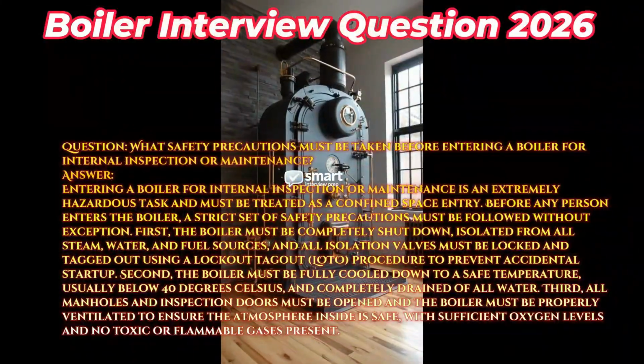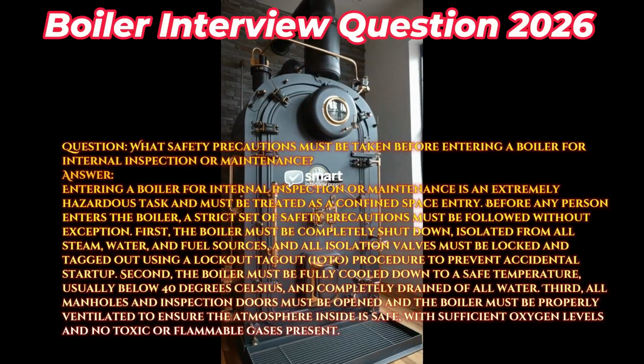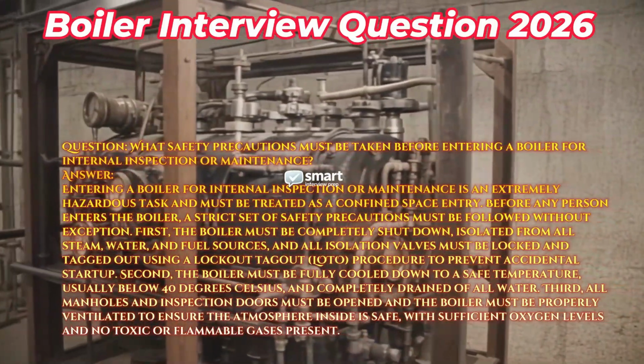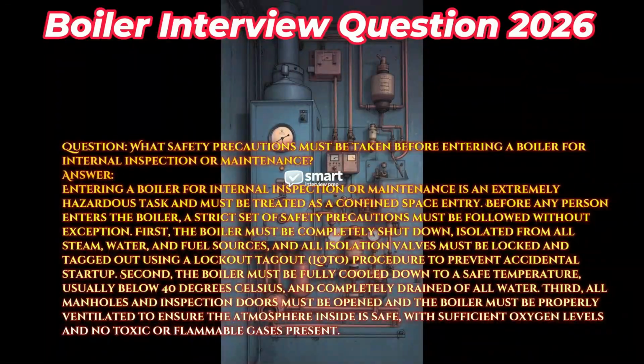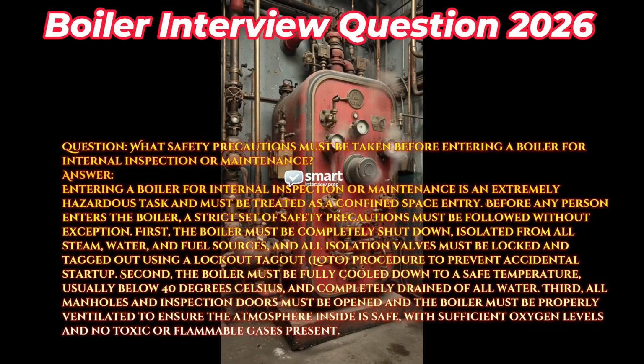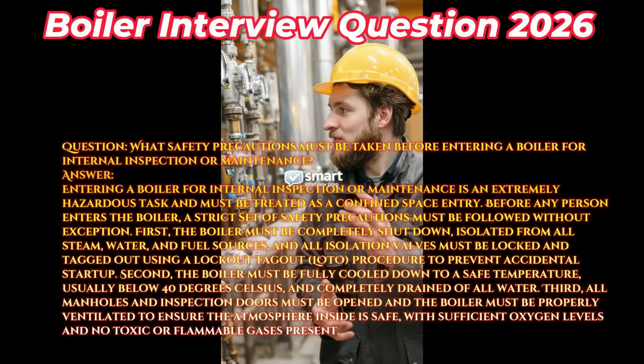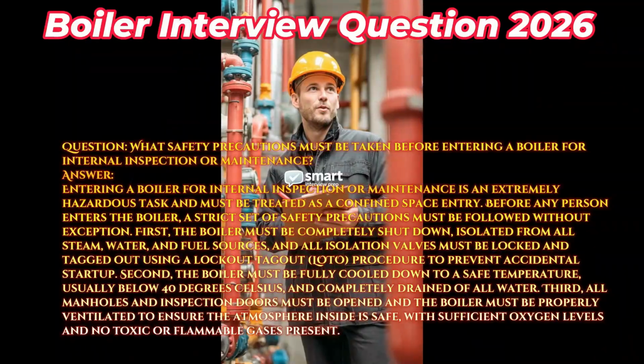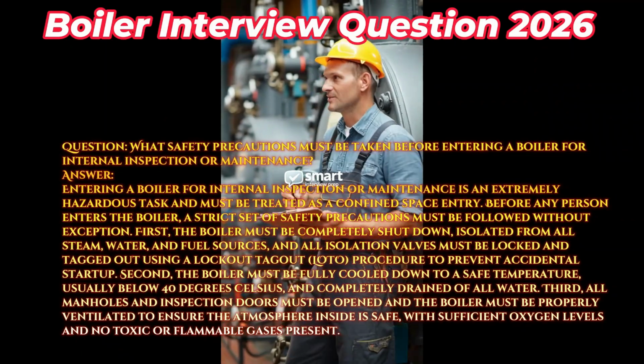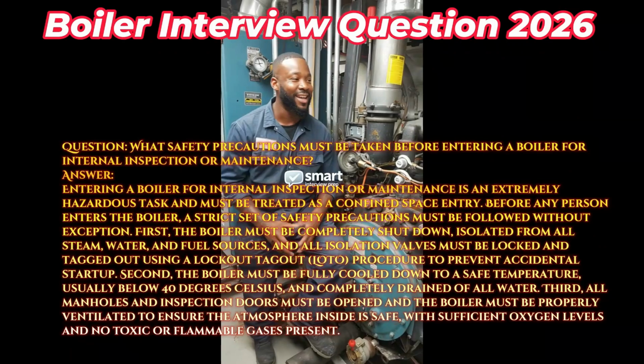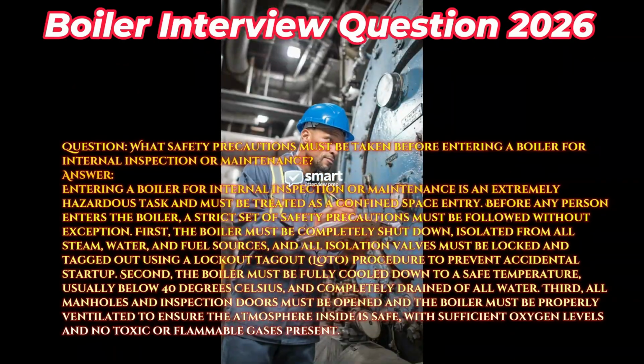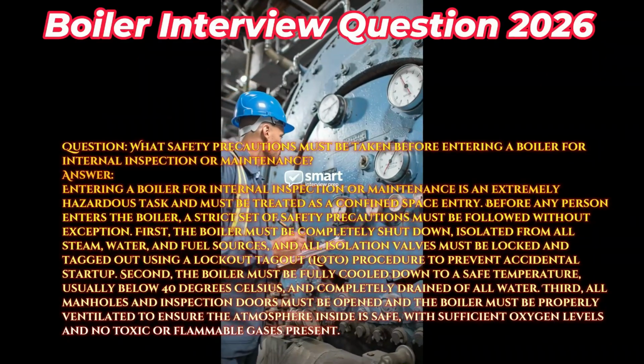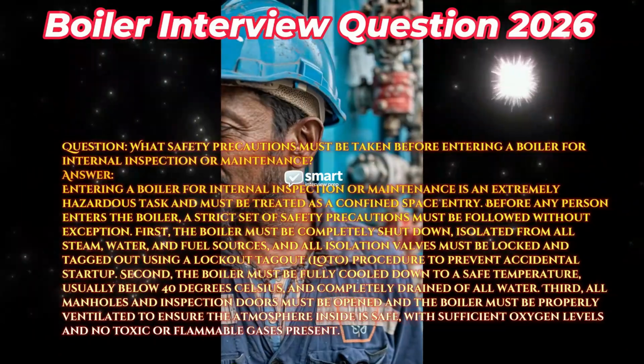Question: what safety precautions must be taken before entering a boiler for internal inspection or maintenance? Answer: entering a boiler for internal inspection or maintenance is an extremely hazardous task and must be treated as a confined space entry. Before any person enters the boiler, a strict set of safety precautions must be followed without exception. First, the boiler must be completely shut down, isolated from all steam, water, and fuel sources, and all isolation valves must be locked and tagged out using a lockout-tagout (LOTO) procedure to prevent accidental startup. Second, the boiler must be fully cooled down to a safe temperature, usually below 40 degrees Celsius, and completely drained of all water. Third, all manholes and inspection doors must be opened and the boiler must be properly ventilated to ensure the atmosphere inside is safe, with sufficient oxygen levels and no toxic or flammable gases present.